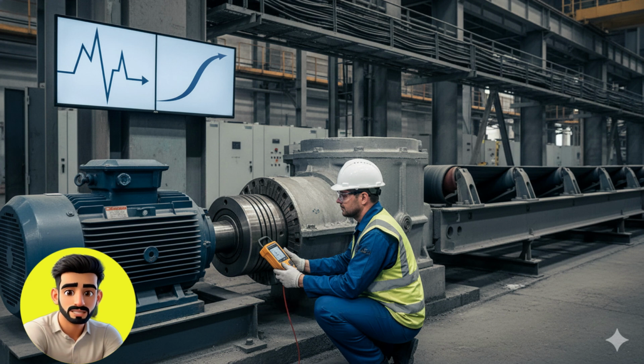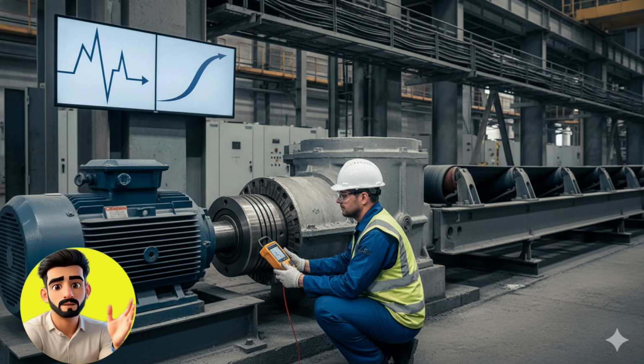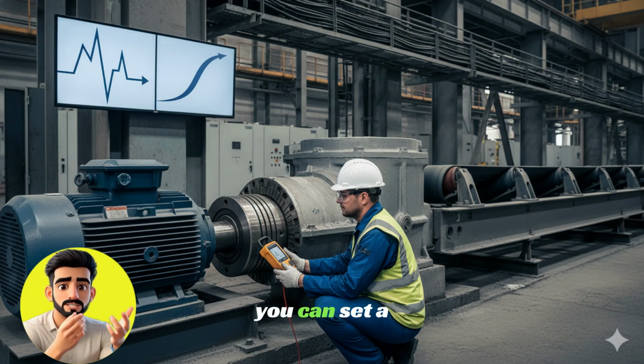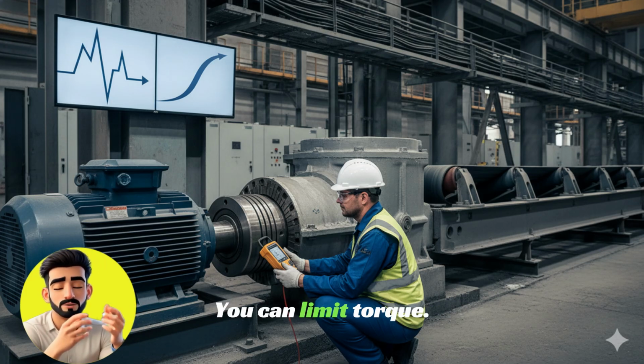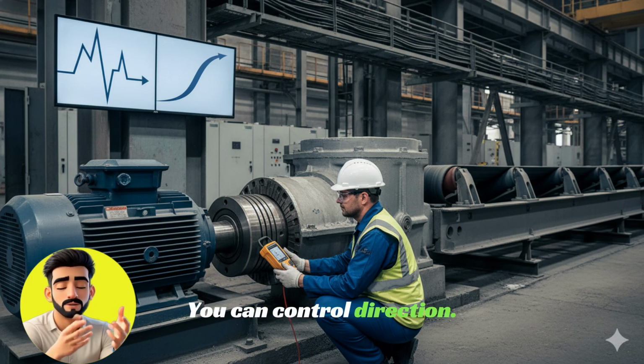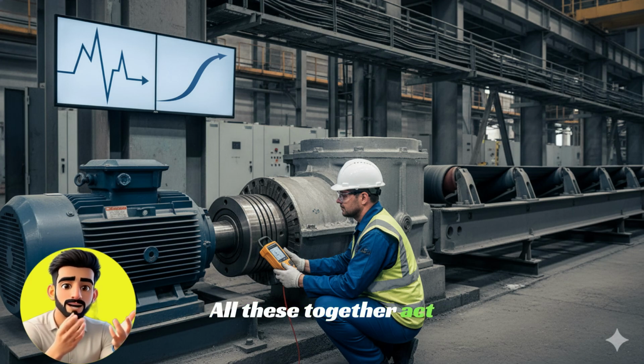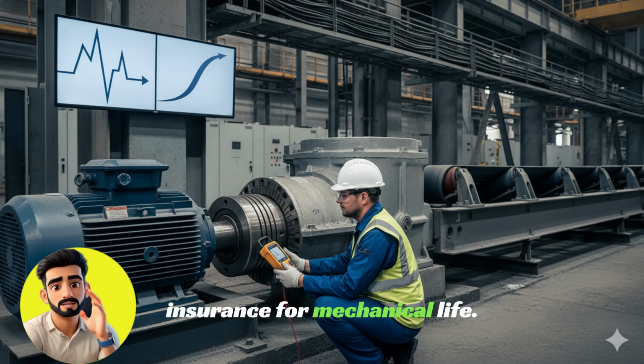In VSD, you can keep the ramp completely controlled. You can give a smooth S-curve start. For heavy inertial loads, you can set a slow start. You can limit torque. You can control direction. All these together act as a kind of insurance for mechanical life.